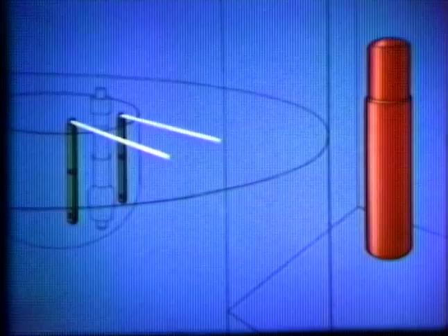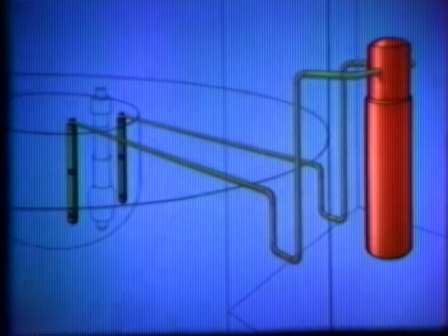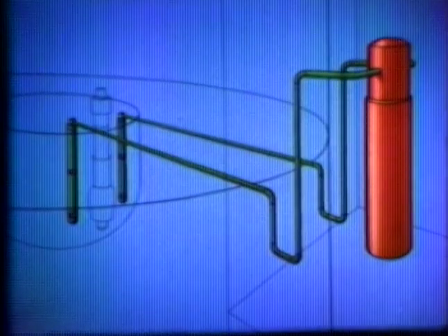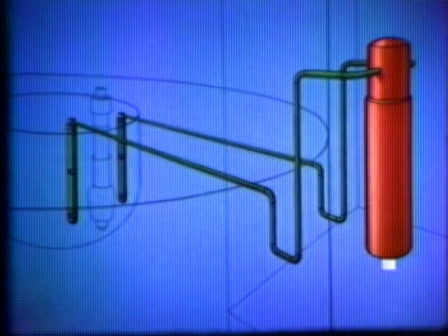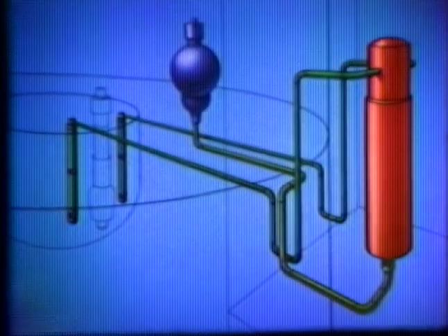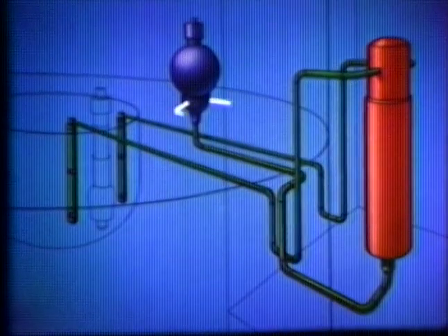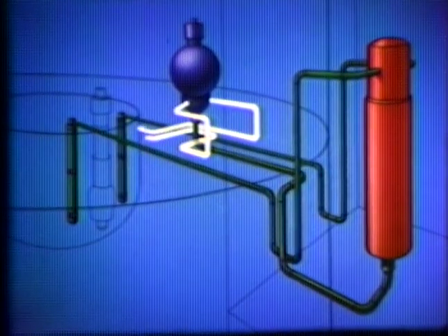The hot sodium at 530 degrees centigrade is conveyed through 2 pipes to the steam generator, where it cools by converting the feed water to steam. It emerges at 350 degrees centigrade in a single pipe, which connects with a secondary sodium pump. The sodium is then discharged to the intermediate heat exchangers through 2 pipes, again with expansion loops.